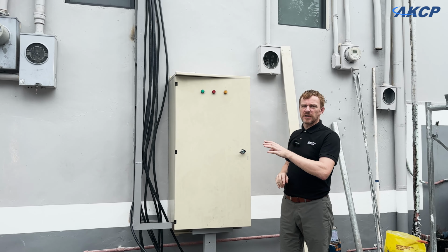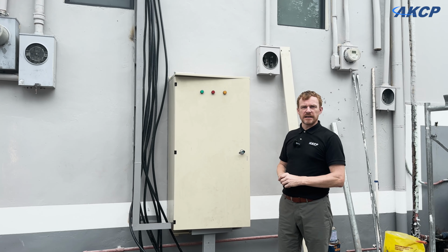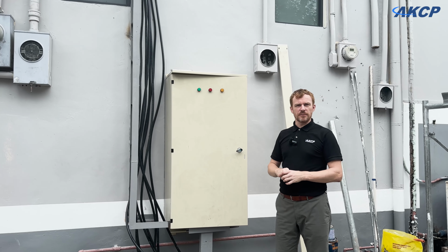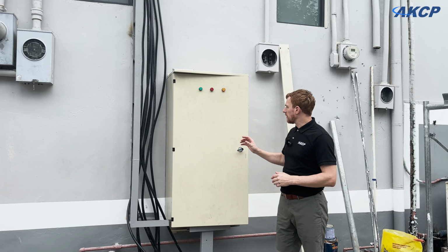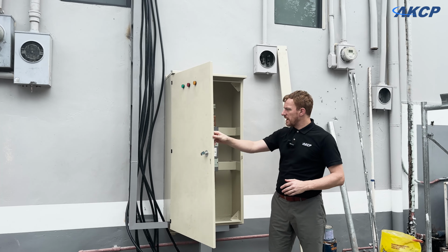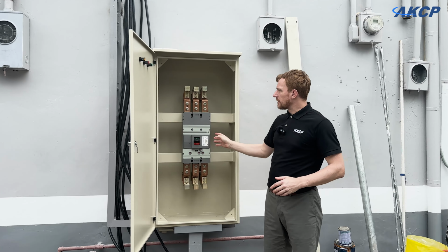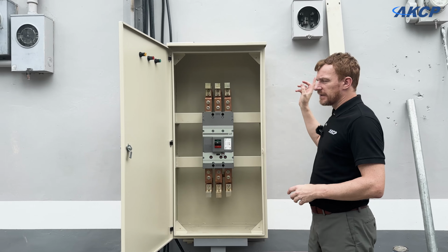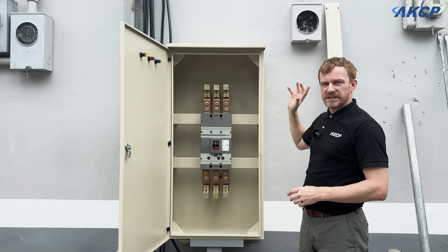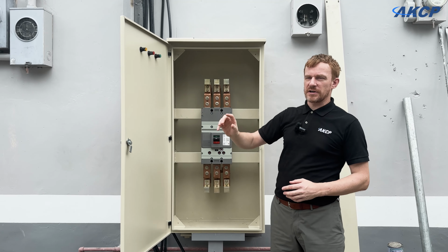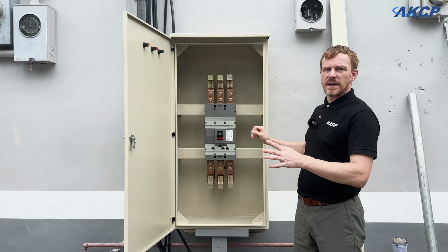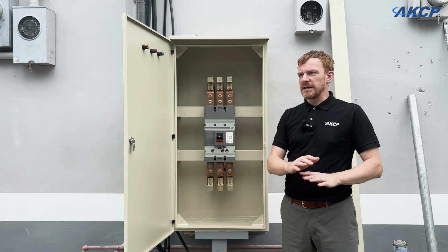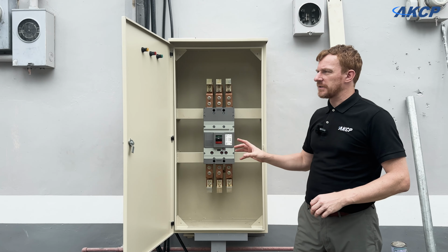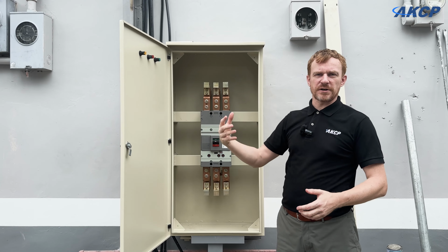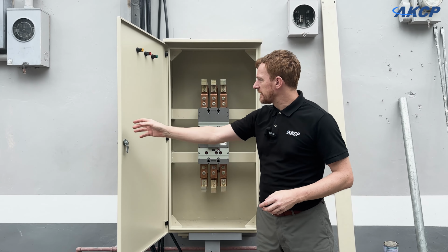If we need to do service on the transformer, then we don't want to have to call up the electric company to shut down the power. So in here, we have a main cutoff switch. This is going to be connected in between the service entrance of the meter and our transformer. So if ever we need to do maintenance, we can shut this off. It'll completely shut down the power to the building. We can then safely open the transformer and do whatever maintenance we need to do.